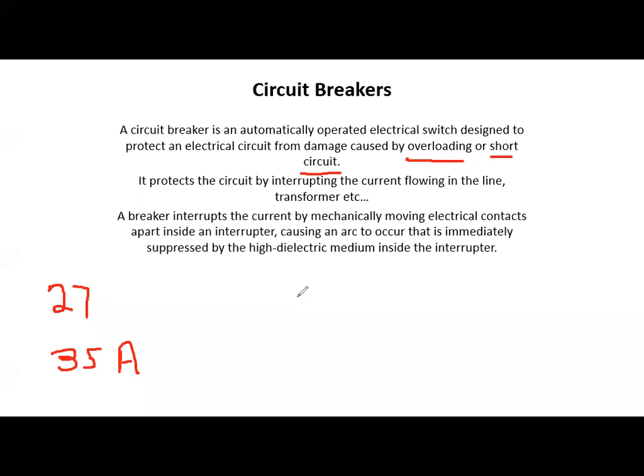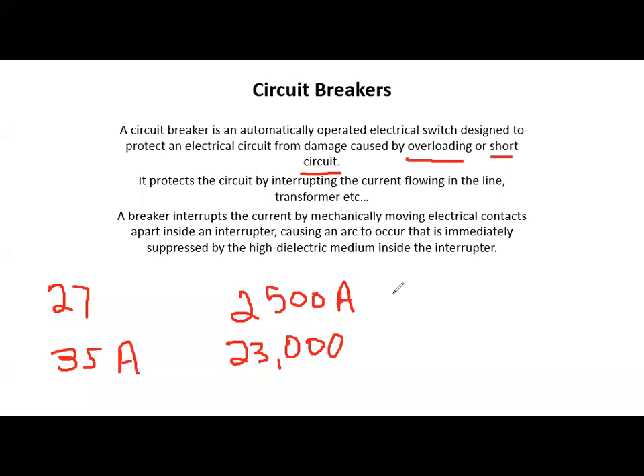I'm just going to give you a few examples. The short circuit current at my house, which is very typical, is right around 2,500 amps. Now, I'm doing this broadcast from a hotel. The short circuit current at this hotel is 23,000 amps. So it all depends on the size of the transformer that is feeding our facilities. This is very important for us to remember: a short circuit or a ground fault is all the current that could flow. We're going to have a rating on that for our circuit breakers and fuses, and we will see that coming up.